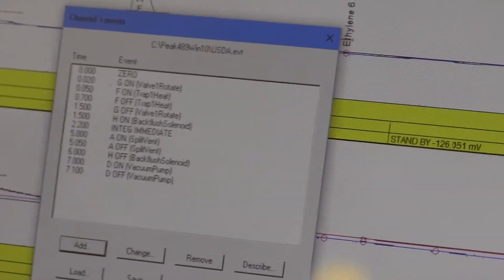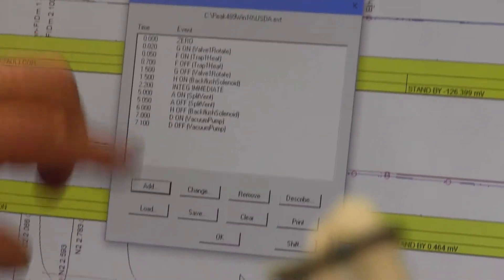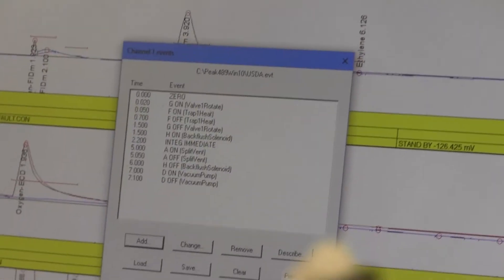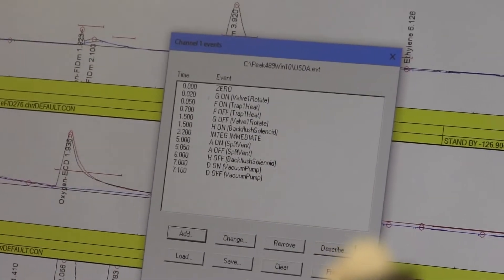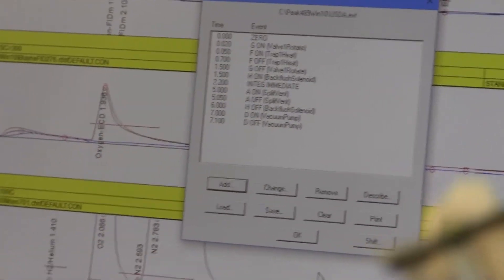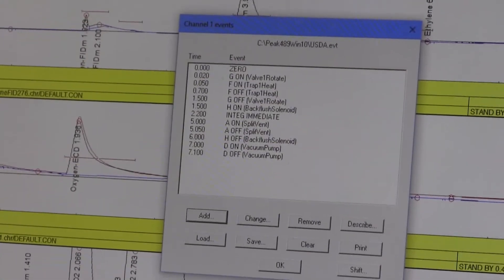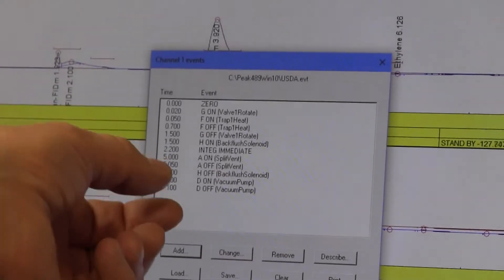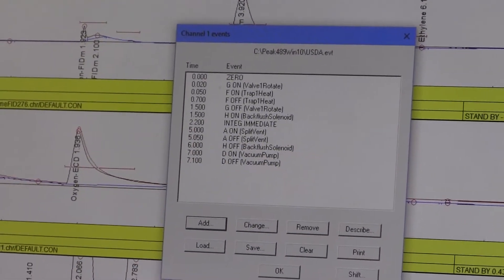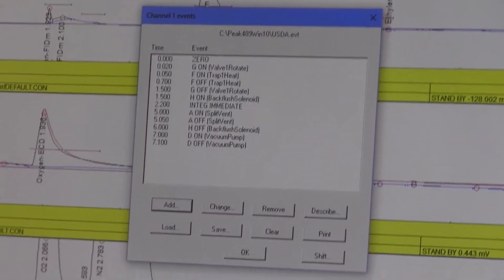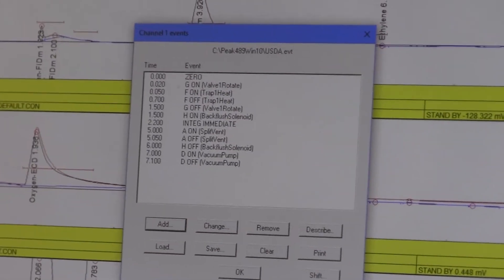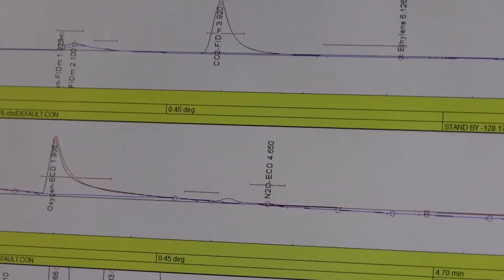So you'd do that sequence many times until you had enough pressures and releases during the course of the analysis, not before the analysis, during the analysis, to clean out the connecting tubing. So maybe you'd repeat that sequence five, six, seven, eight, nine, ten times, as many times as you thought necessary. So that's how this is supposed to work.